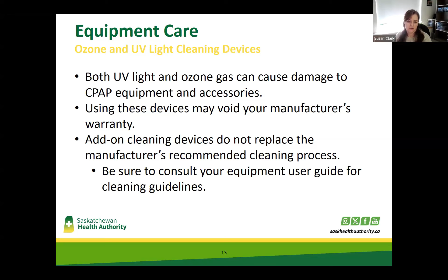The other caveat to these is that the add-on cleaning devices don't replace the manufacturer's recommended cleaning process. So even if you were to use these devices, you still have to follow the manufacturer's recommended cleaning processes. So it doesn't necessarily save you time, because you still need to be cleaning your equipment. Again, be sure to consult your user guides. Okay, next slide.